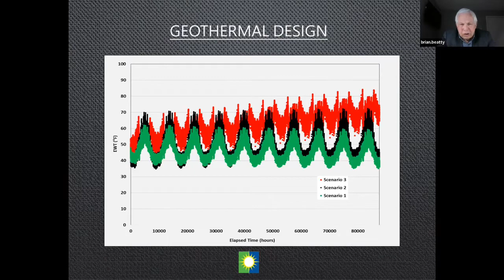cooling, you end up heating the ground up. So that year after year, that red curve is increasing. That means the borehole field is heating up. And we have several projects right in the downtown Toronto area where that exactly is happening. That would simply mean that the system was not designed properly in the first place. So we have that problem of heating up the borehole field. The green curve at the bottom is what you should strive for. It's not heating up, it's just more or less staying steady from left to right. And that's the ideal situation for a perfectly balanced energy load. Next slide.